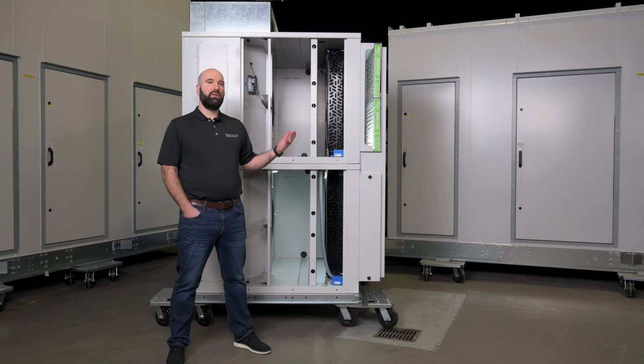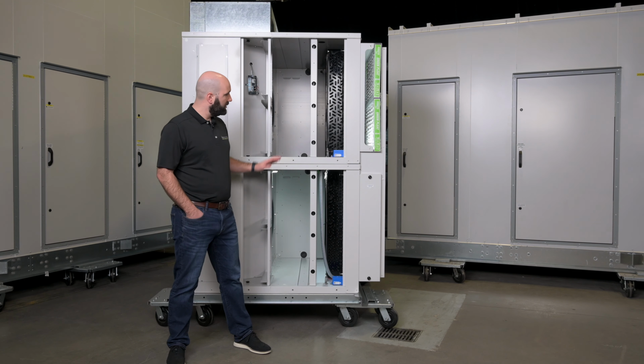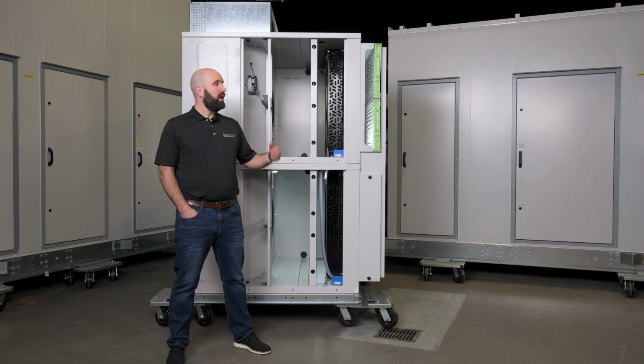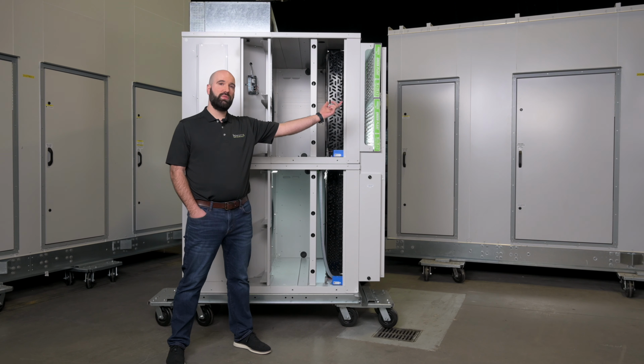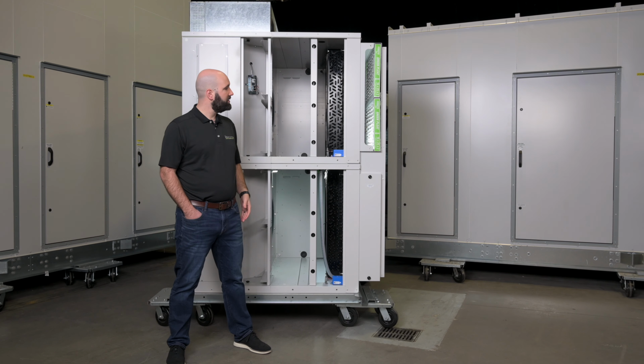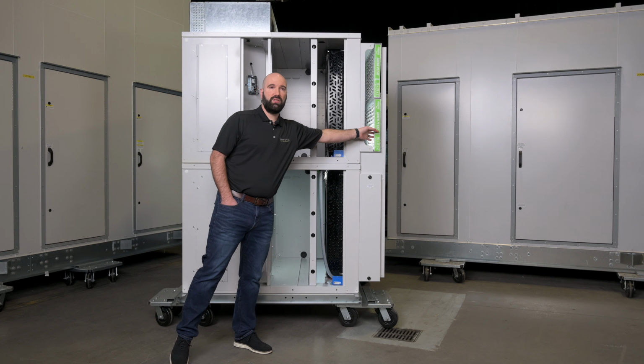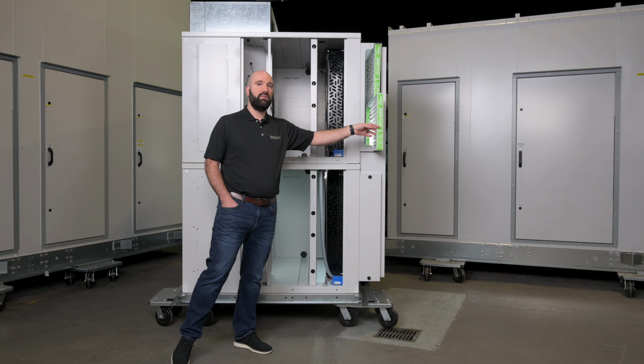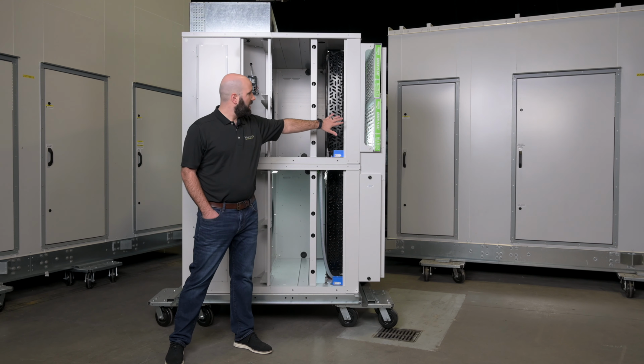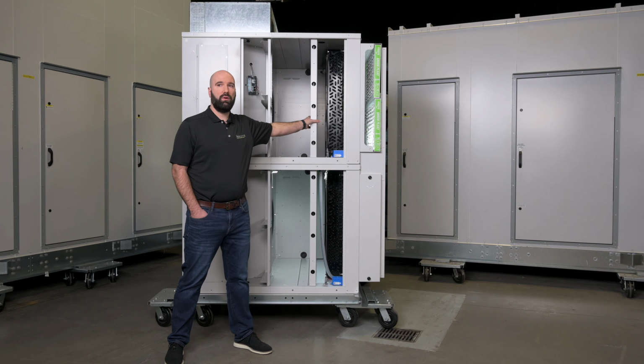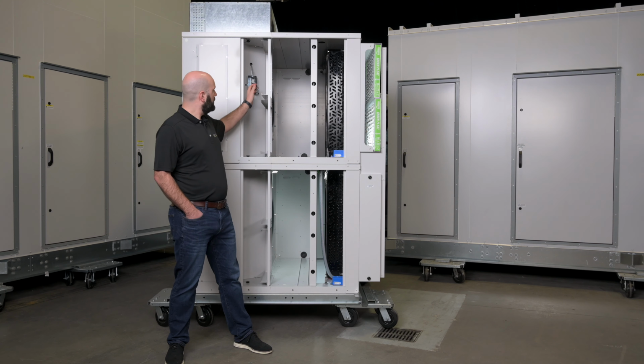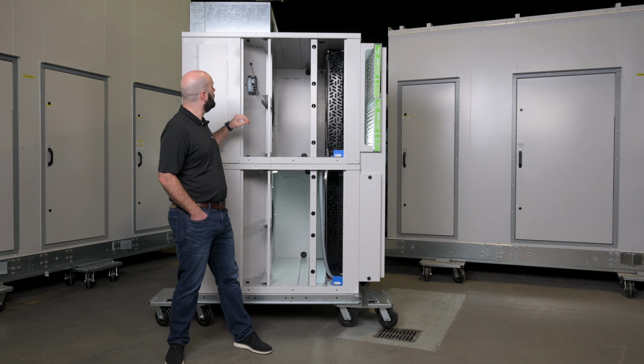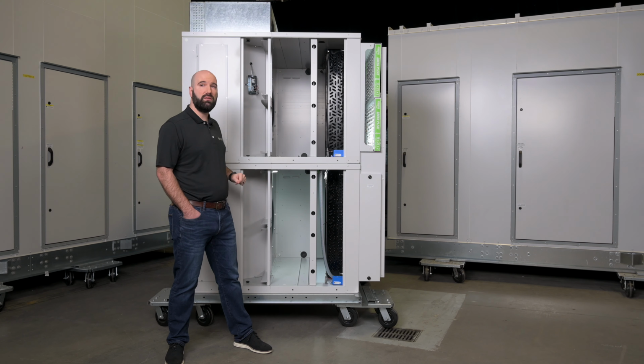Let's spin again and we'll take a look at the coil set. So on this side here you can see the coil set of these two, again, completely independent refrigeration decks. As the air travels through the machine, it comes from the return air section on my left here, through these filters. These are standard size MERV 13 filters, again providing excellent filtration for your unit. We've got the evaporator coil, microchannel reheat coil, and we've got the fan. You can see behind me here an air proving switch to ensure that in the event of a fan failure, we're not trying to heat.